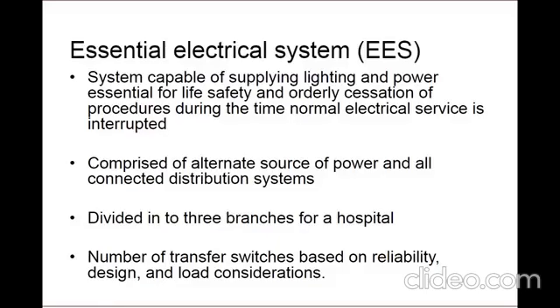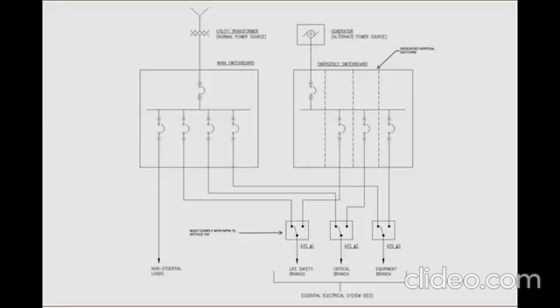It provides details on the minimum quantity of ATSs required. However, any of these branches are permitted to be divided into sub-branches for added reliability or as required by the connected load design. Here is a very simplified diagram of an EES for a hospital. And if you are familiar with older versions of the code, you will notice a change in terminology here. Formerly, the critical and the life safety branches were grouped together and called the emergency system. This has been completely removed in the 2014 NEC, and now all 3 branches are referred to collectively as the EES. This was a change to both the 2014 NEC and the 2015 NFPA 99.